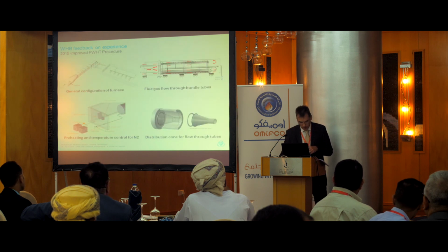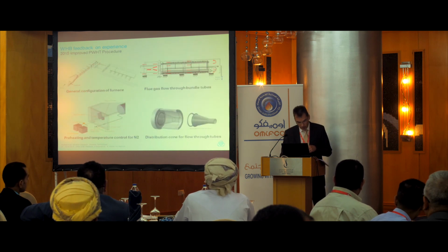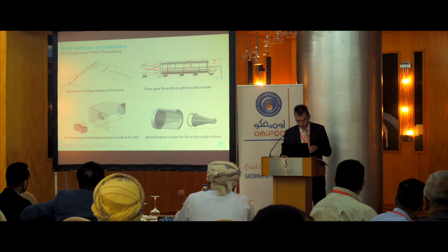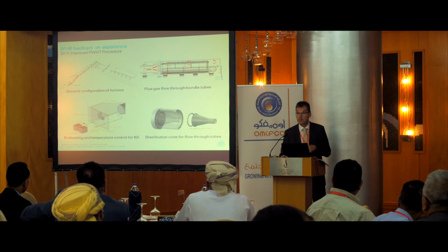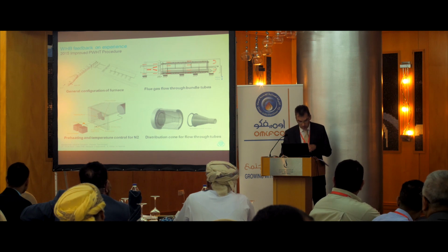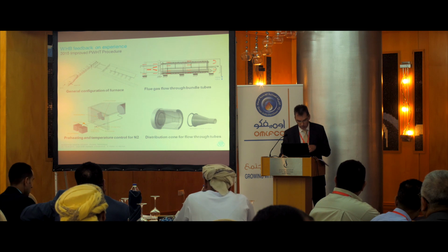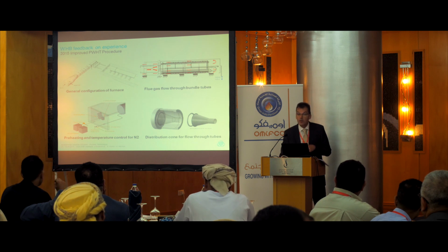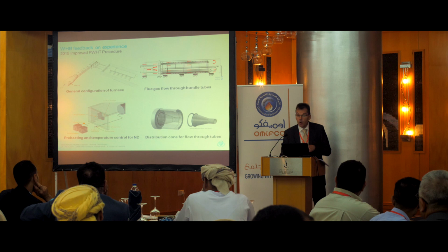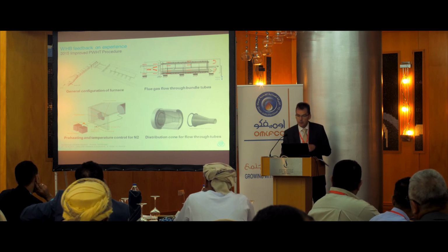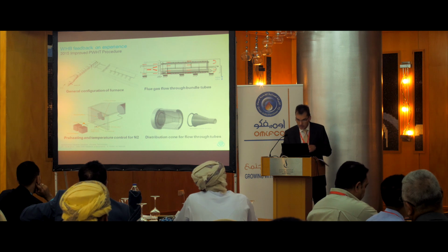Summarizing, for heat treatment, for all future fabrication, it was decided to accept only post-weld heat treatment with the whole bundle, including the auxiliary shell, inside the furnace. Furthermore, additional circulation of hot gas through the tube bundle is effected by a temporary internal cone in the channel. We also changed the heat treatment so that hot gas also goes inside the U-tubes, so that we have a uniform heat distribution outside the bundle and in the tubes.